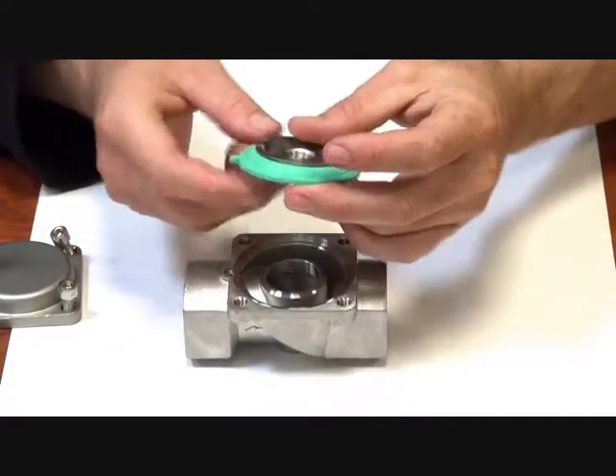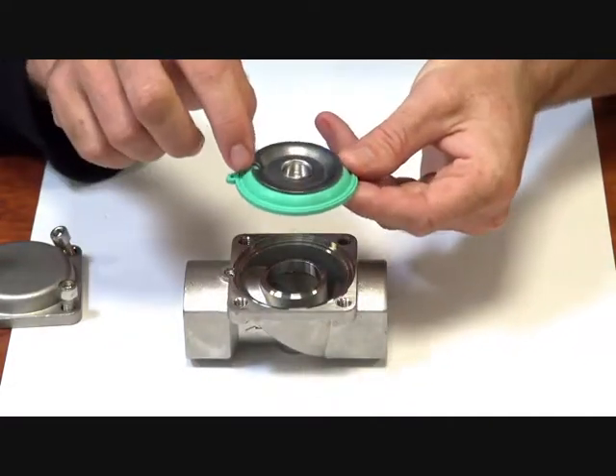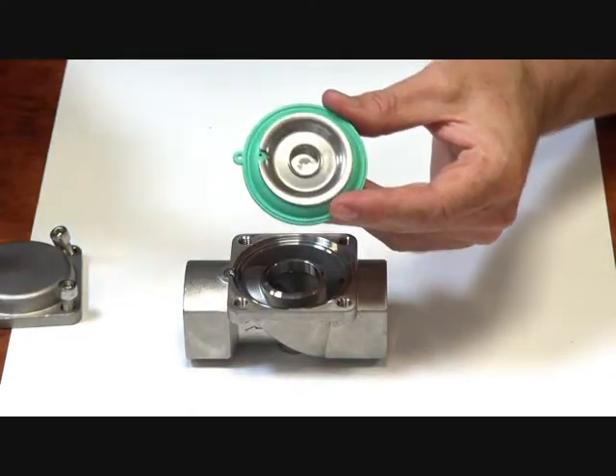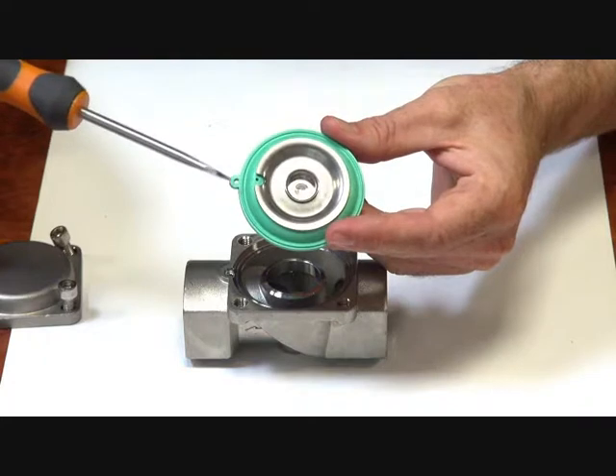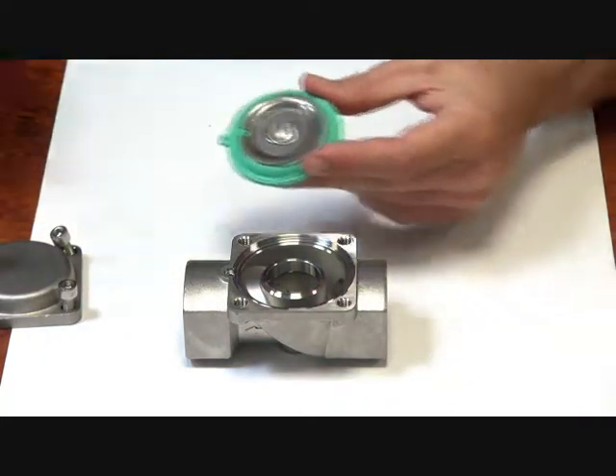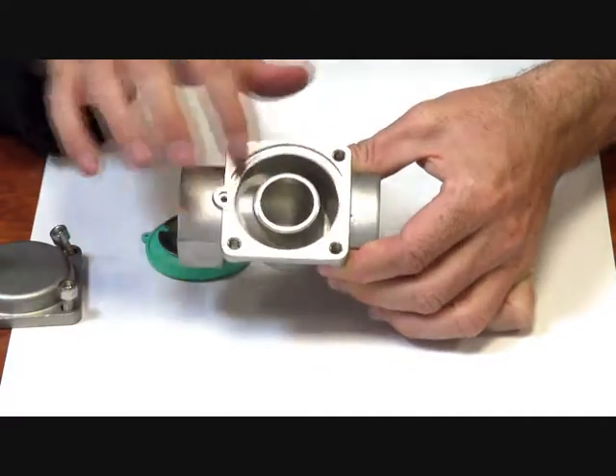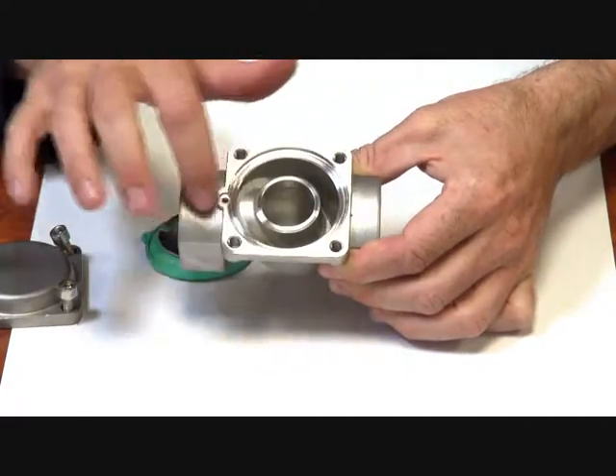Now if you're maintaining this valve, it's important to note that this little hole here in the diaphragm is clear. Both of these holes are clear. Also check the seat, the machine seat, to make sure this is clear. So here, this is where water goes, flow path down and out.